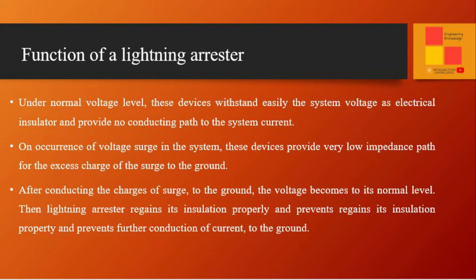Under normal voltage levels, these devices easily withstand the system voltage as electrical insulators and provide no conducting path to the system current. On occurrence of a voltage surge in the system, these devices provide a very low impedance path for the excess charge of the surge to the ground. After conducting the charges of the surge to the ground, the voltage returns to its normal level. Then the lightning arrestor regains its insulation property and prevents further conduction of current to the ground.